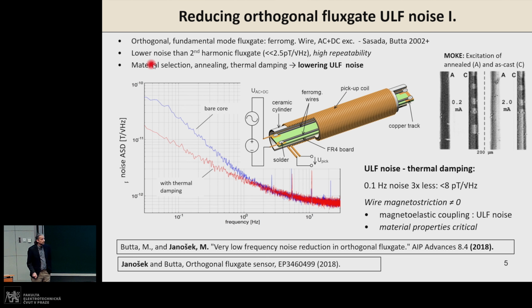The key point to reach lower noise than originally Sasada had, which was about 10 picotesla, is to select the proper material, probably anneal the core. And we have found that not only the annealing, which we can see the result on the right-hand side from a MOKE observation, but we have found that the ultra-low frequency noise of this orthogonal first harmonic fluxgate depends very much on temperature instabilities. And with proper thermal damping, we were in the first step able to reduce the ultra-low frequency noise about 3 times. Of course, it wasn't that easy.